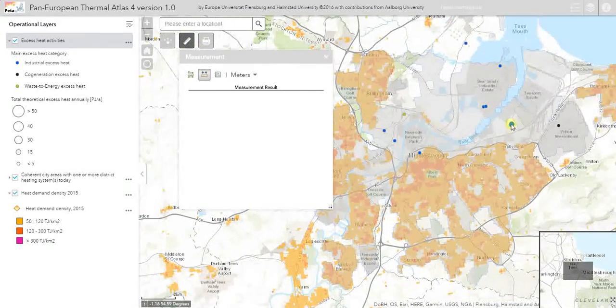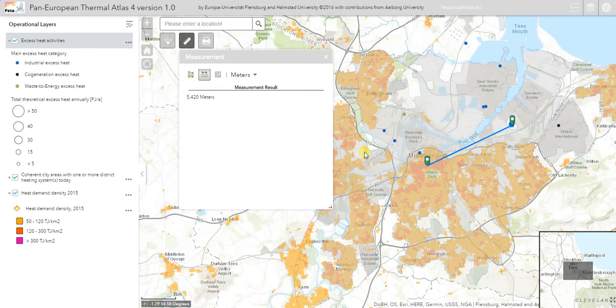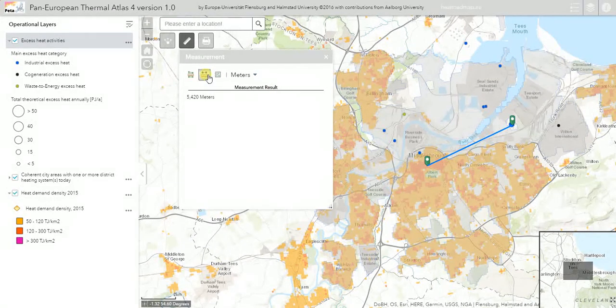The plant with the highest excess heat is the logical starting point. The city center is the most attractive place to begin developing district heating because of its high heat densities. Measuring the distance from the plant to the city center, I can see it is about five kilometers — which in district heating terms is very, very reasonable. The largest CHP plant in Copenhagen is around 12 kilometers from the city center, so this is very manageable with existing technologies.